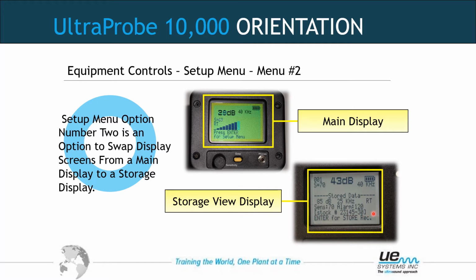In between the brackets, you see a stock number. That could say motor 1 inboard bearing or motor 1 MIB. That's the asset nomenclature that you named that information in the route in the Ultratrend DMS software and was loaded to this unit. Whoever named this, they named that asset with that stock number. Then the function bar, again, it does not say press enter, but it's the function bar again. It says enter for store record.